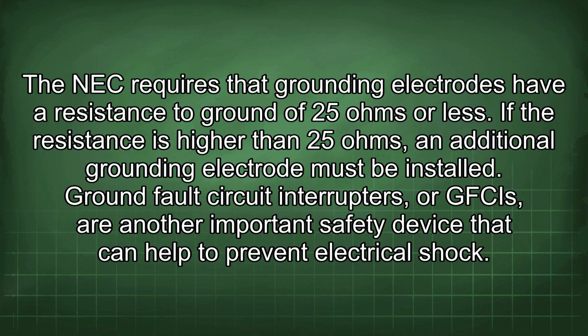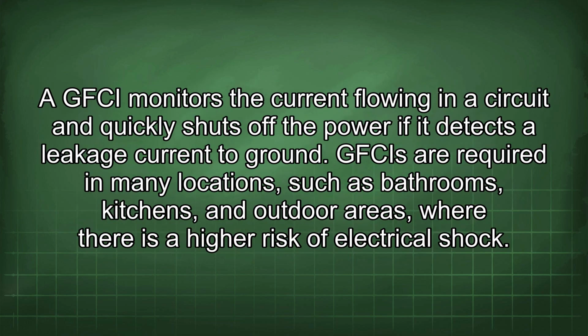Ground fault circuit interrupters, or GFCIs, are another important safety device that can help to prevent electrical shock. A GFCI monitors the current flowing in a circuit and quickly shuts off the power if it detects a leakage current to ground. GFCIs are required in many locations, such as bathrooms, kitchens, and outdoor areas, where there is a high risk of electrical shock.